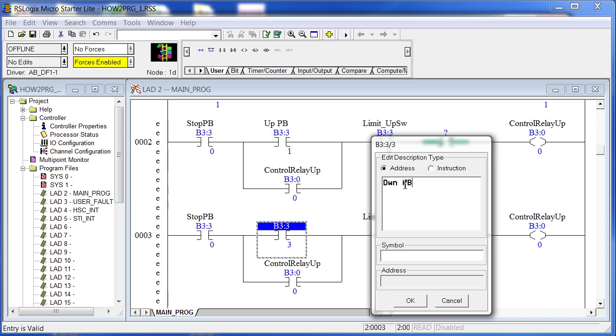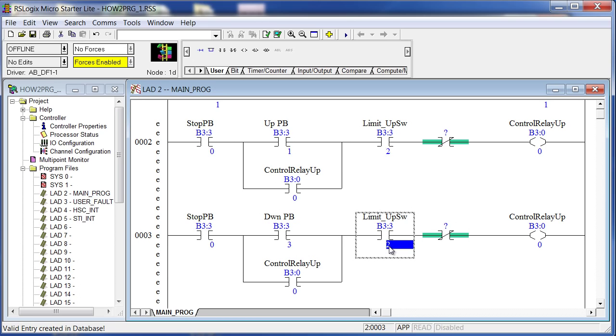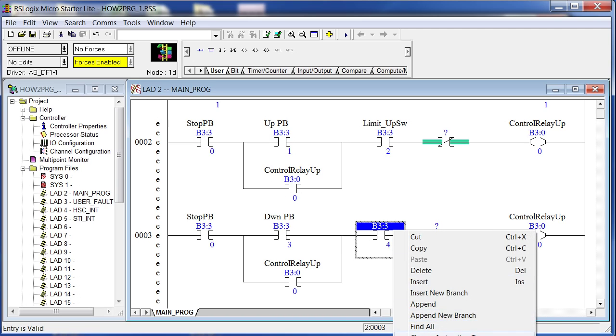Dragging things around gives us our interlocking logic. I'll hit Verify File. These rungs look pretty much like the wiring diagram: stop for either up or down; up button, up limit switch, interlock with the control down relay, interlock with the control up relay. Then down, down, up, up — I see one mistake: this contact should be Control Relay Down, not Control Relay Up, because this seals in the down push button.